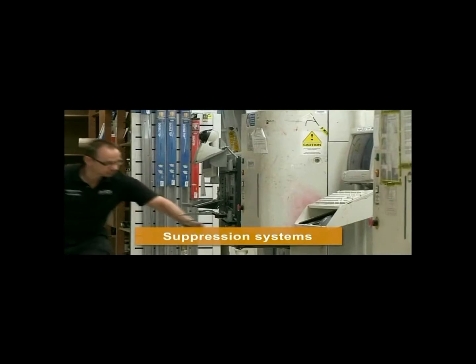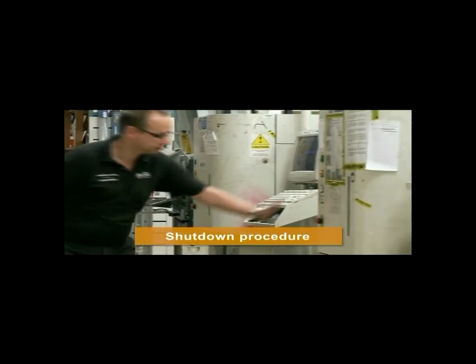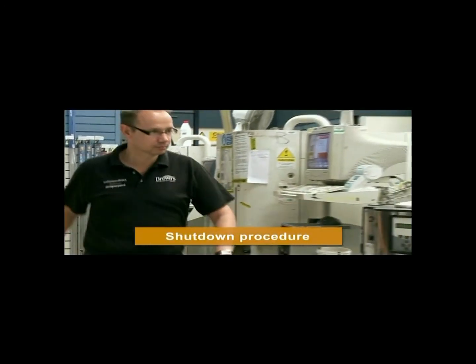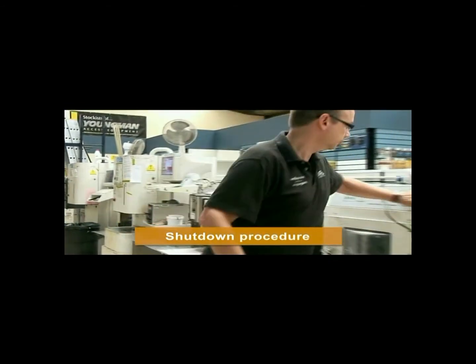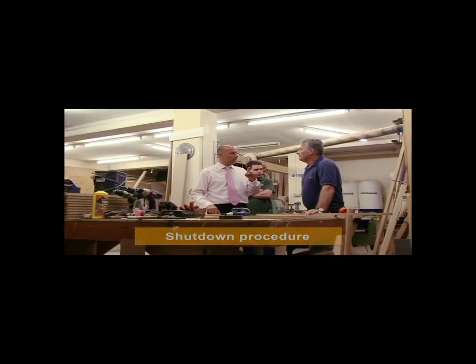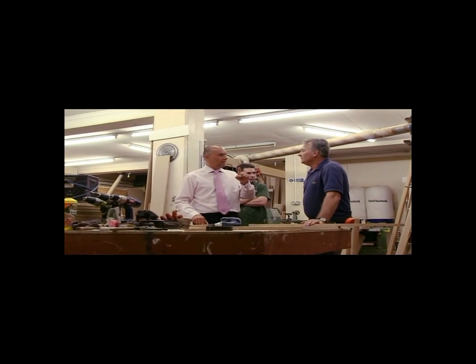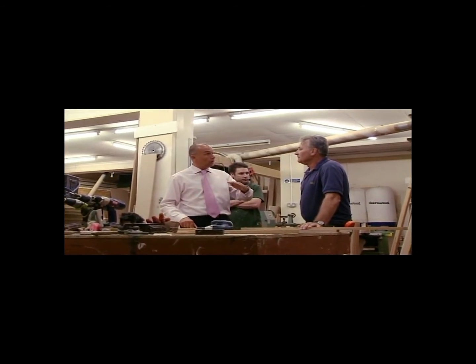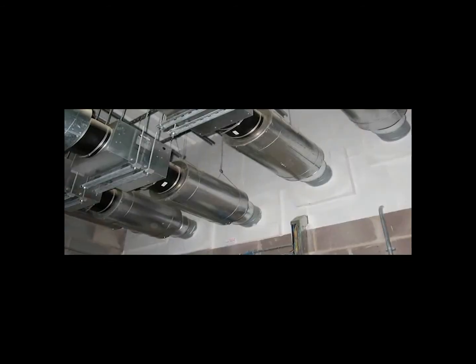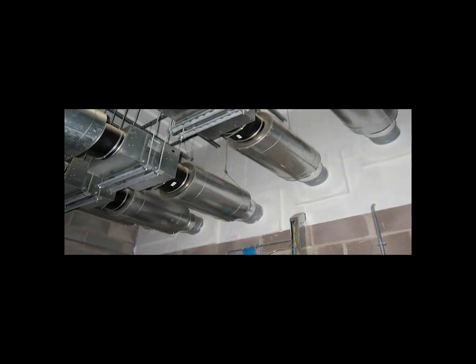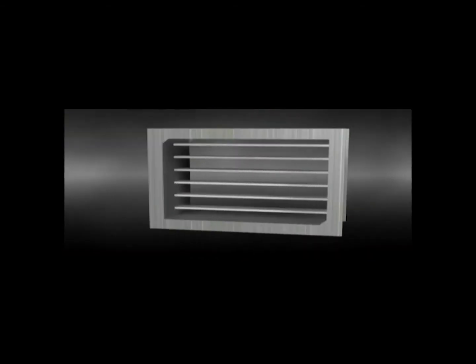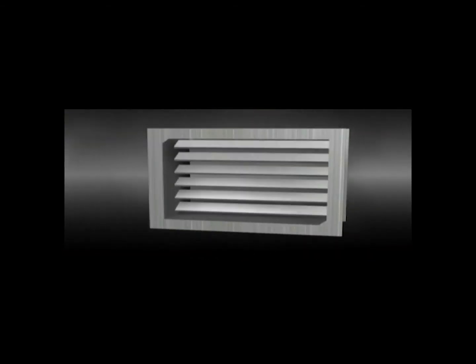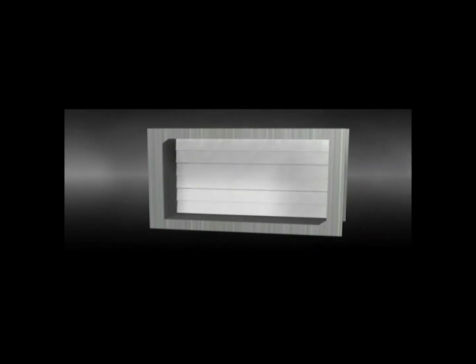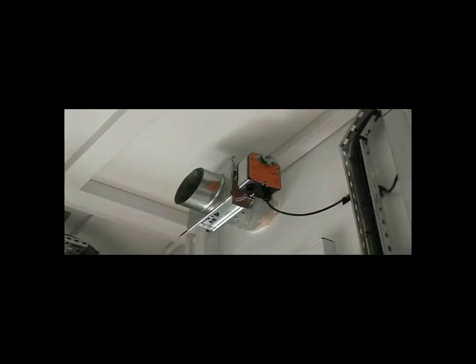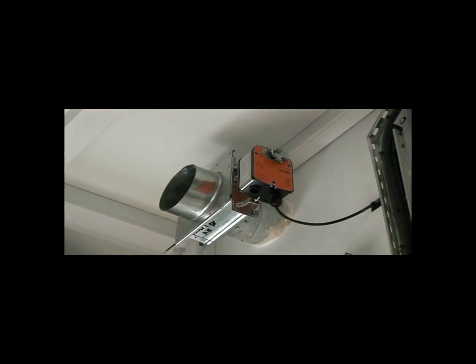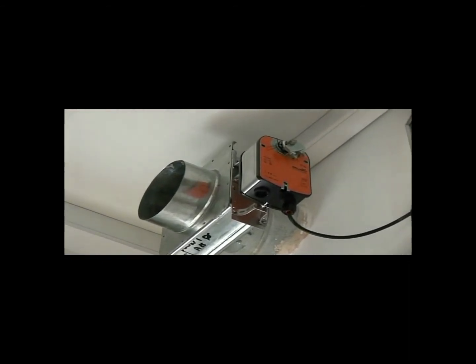Consider any other management procedures, for example, equipment shutdown or security measures that are relevant to your place of work. Ensure existing precautions are adequate and consider what else might need to be done. For example, buildings with large ventilation systems may be fitted with dampers at compartment lines which shut down the airflow through the ducting when the fire alarm is activated. These should be checked regularly by a competent person to ensure they are operating correctly.